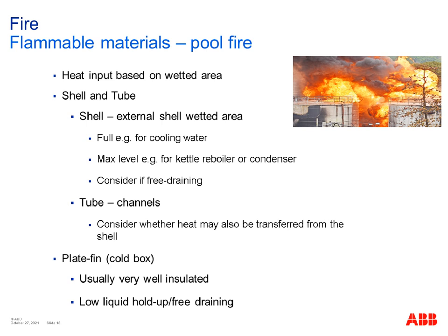For a plate fin exchanger, these are normally well insulated. If it's a free draining piece of equipment, then you won't have liquid hold up, and there'll be no actual wetted surface area, so there'll be no heat input from the fire. In that case, you can eliminate fire for this type of heat exchanger. But as with anything else, you need to think through your scenario for your particular item of process equipment.